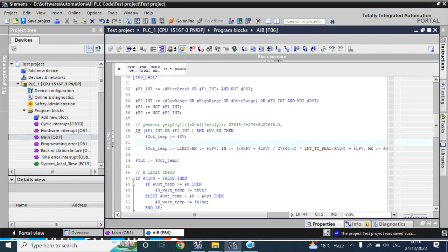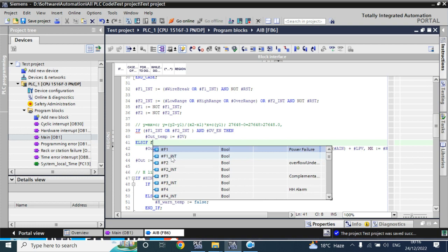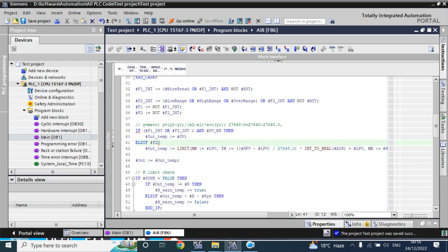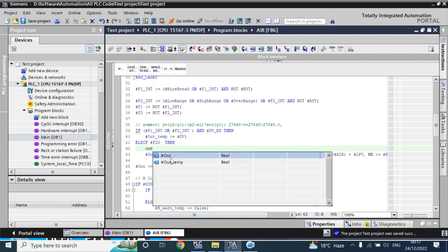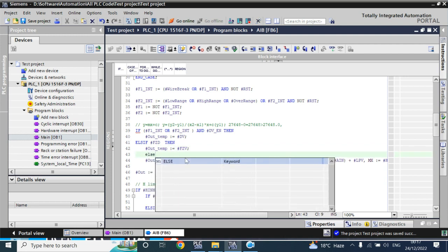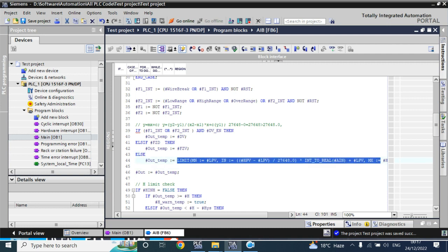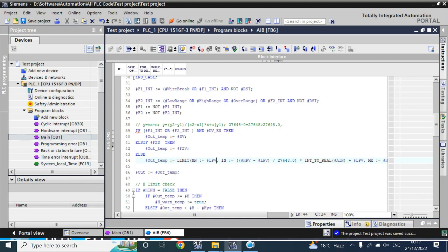The second case: ELSE IF freeze is chosen, then the temporary output will take the value from the frozen value. Otherwise, in the ELSE branch, the temporary output will be calculated from the linear line equation, limited by LPV and HPV. We then close the IF instruction with END IF.